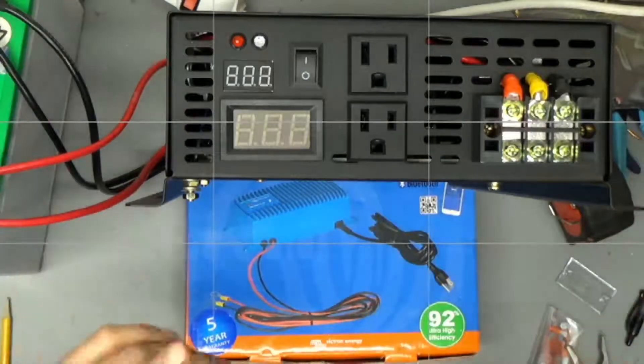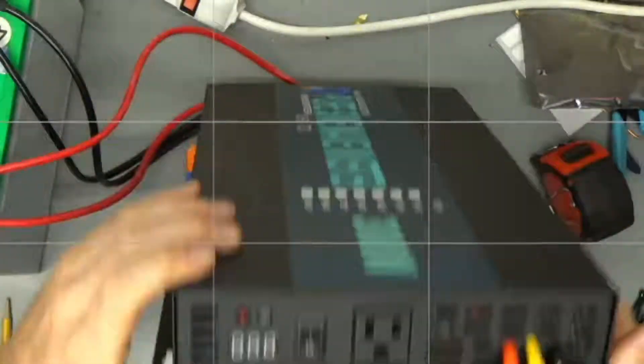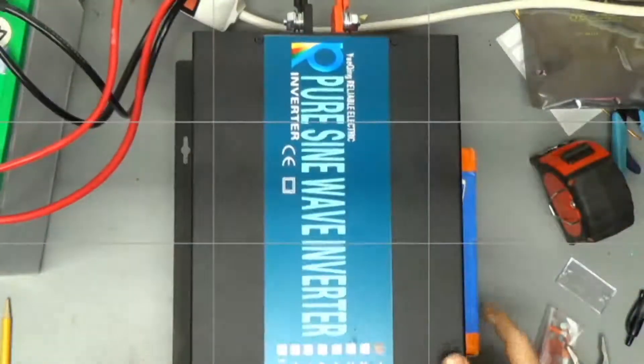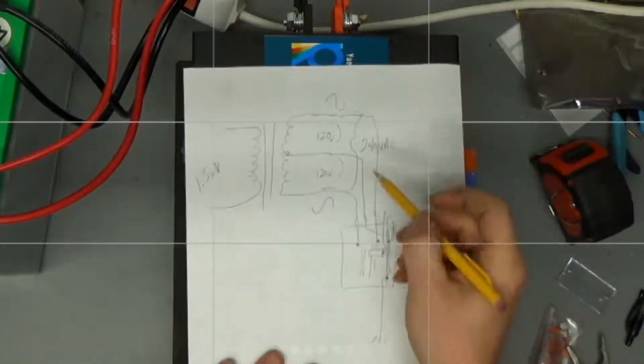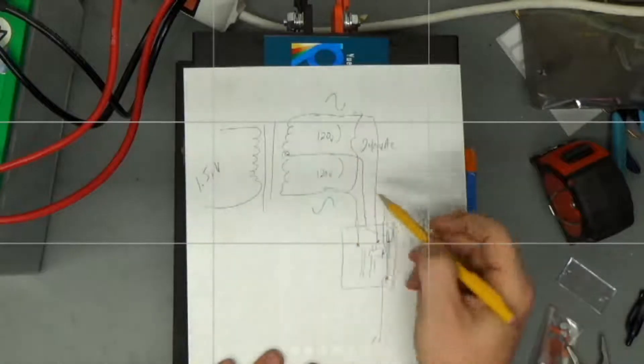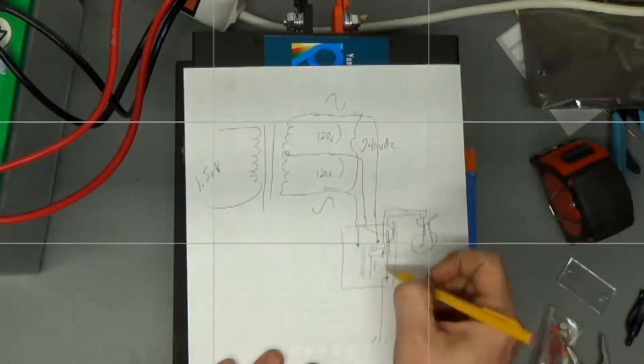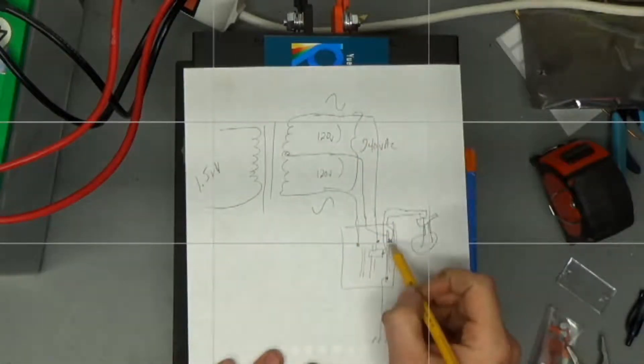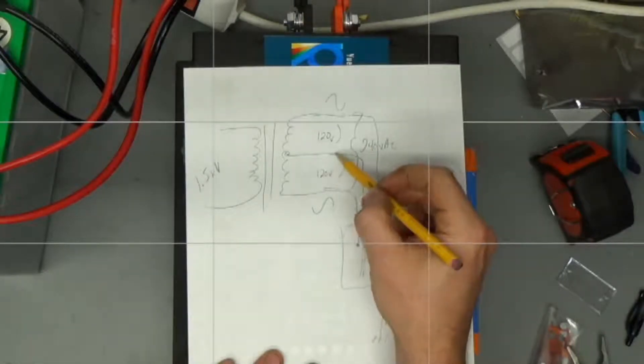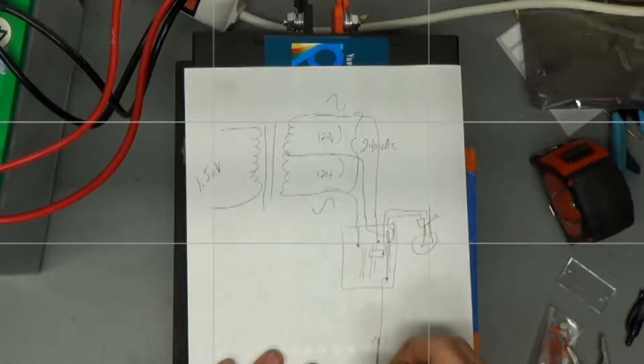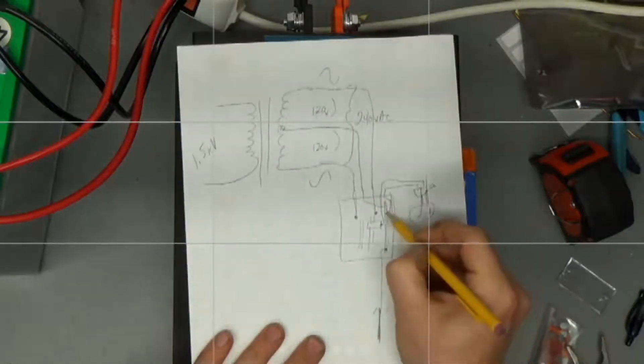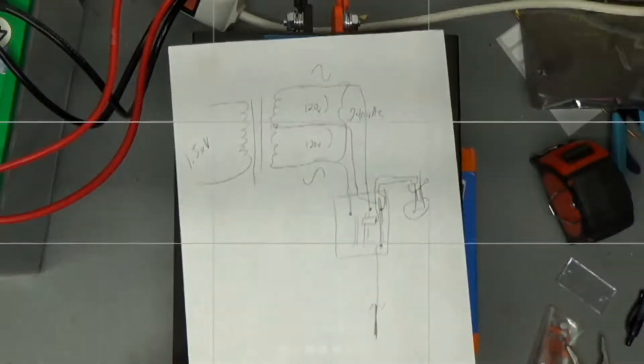But the problem comes when you try to hook one of these things into your electrical panel box because as we discussed before, when your service gets terminated here at your panel box, the neutral from the transformer outside and the ground, the ground rod outside of your house are bonded together on this bus bar.